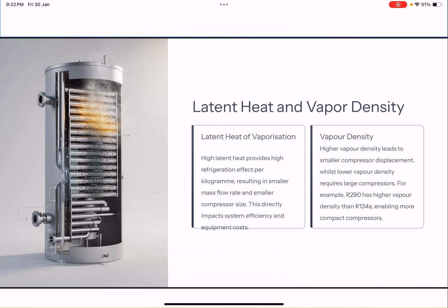The next thermodynamic property which should be considered in selection of refrigerant is the vapor density or the specific volume of the vapor. You know that specific volume of the vapor is the reciprocal of vapor density. So higher vapor density means a lower specific volume, and the lower specific volume means the smaller compressor displacement. If the vapor density is lower, it means that the specific volume is higher.